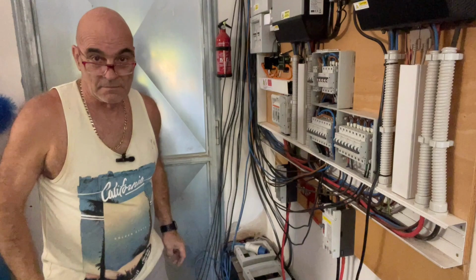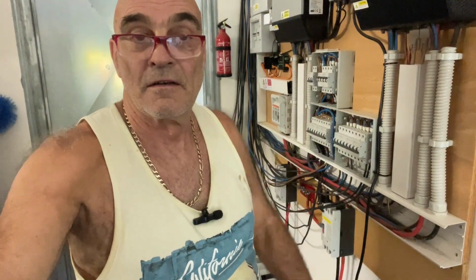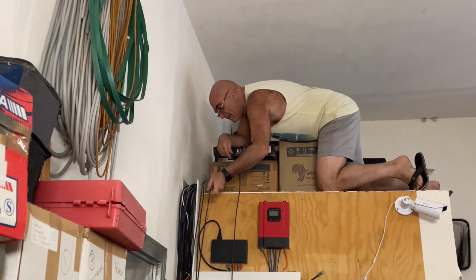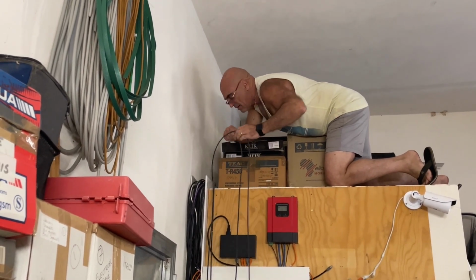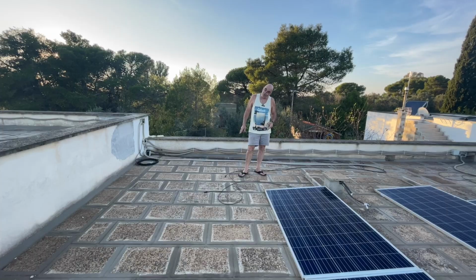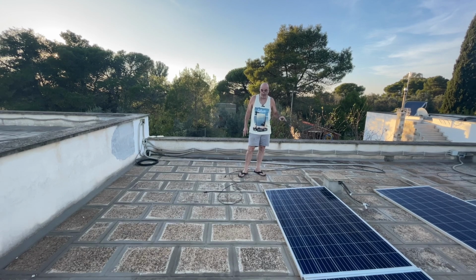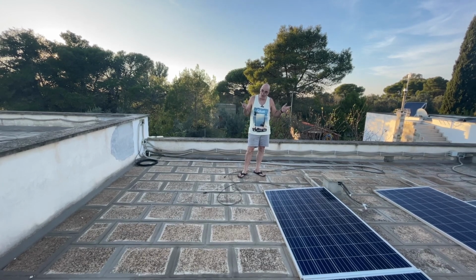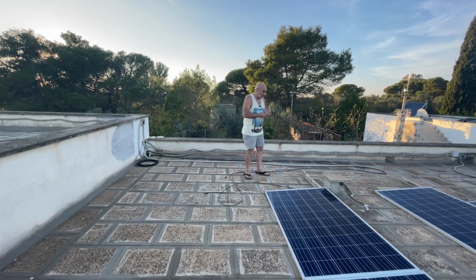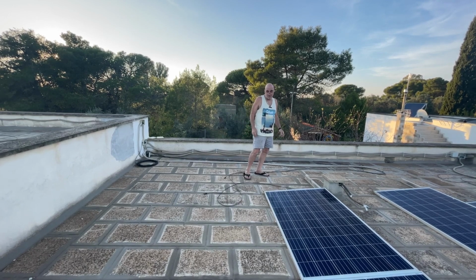So now I'm going to climb on the roof - not that roof, this roof over here. I've got 9 pairs of cables running up to connect to 9 strings of panels. I only need 4 pairs of cable coming up to connect to 4 strings, so I'm pulling out 10 pieces of cable.